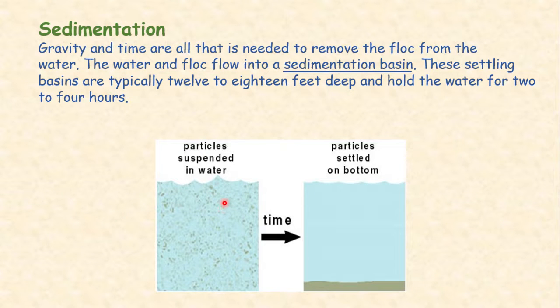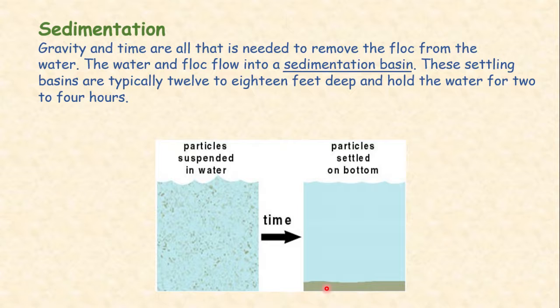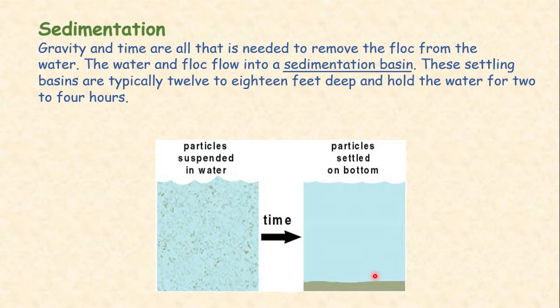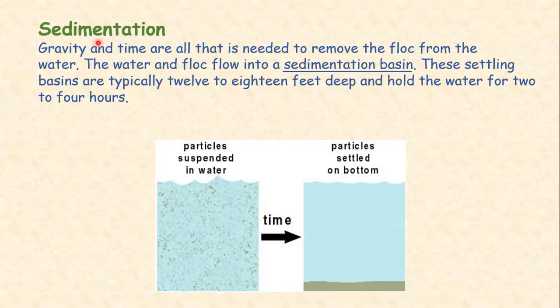In sedimentation, small particles are suspended inside the water and need time to settle at the bottom. Gravity and time are needed to remove the floc from the water. The water and floc flow into a sedimentation basin. These settling basins are 12 to 18 feet deep and hold the water for 2 to 4 hours. The time can vary according to the situation. The fine or suspended particles settle at the bottom — this is named sedimentation.